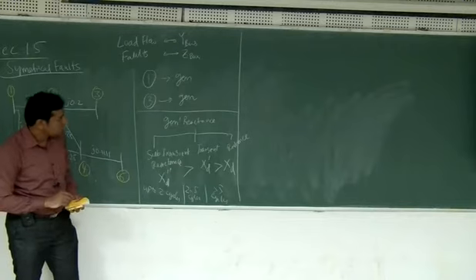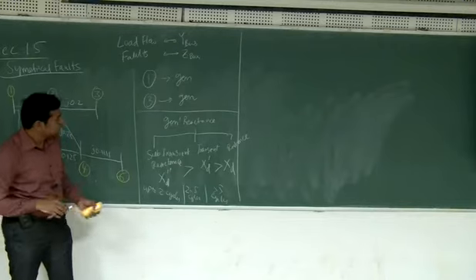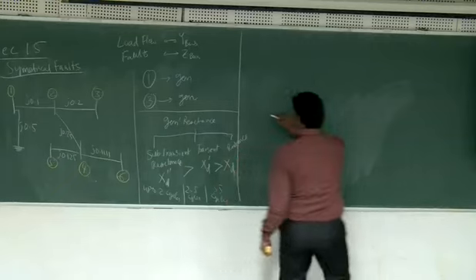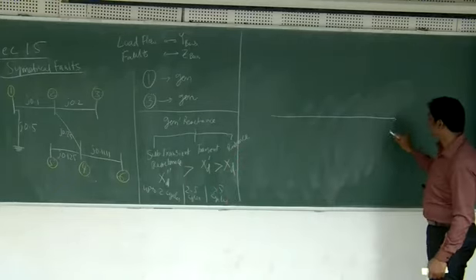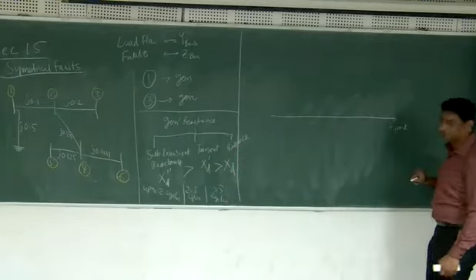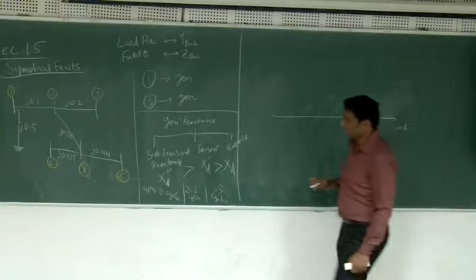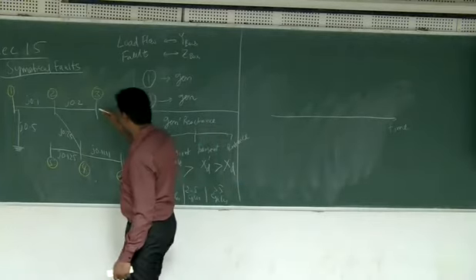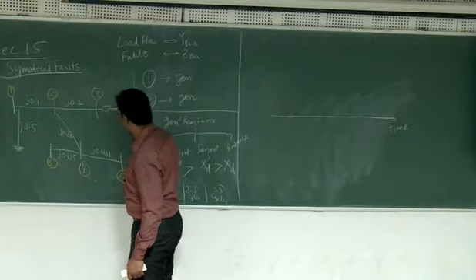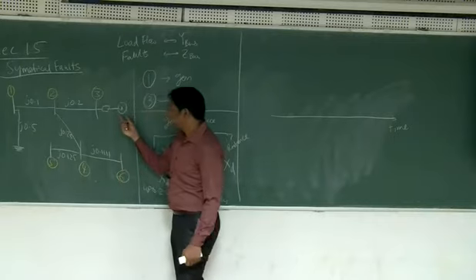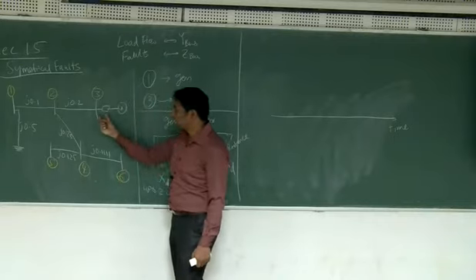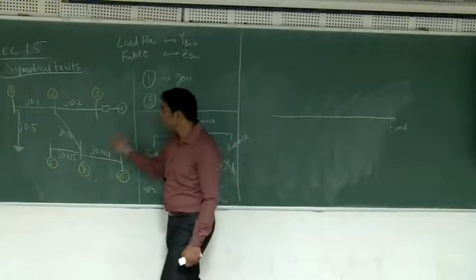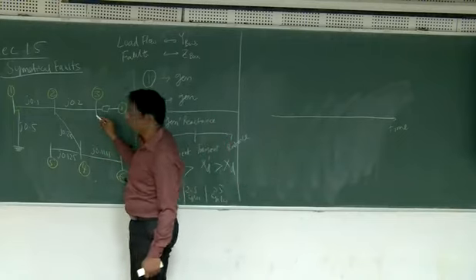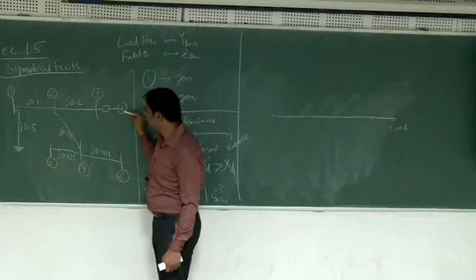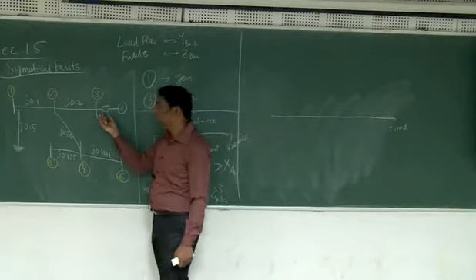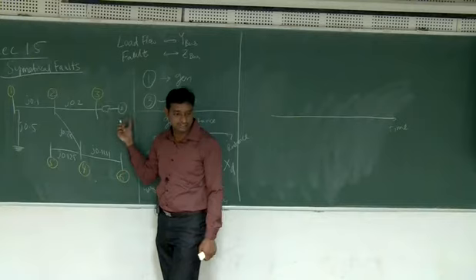Okay, I think at this time we can also discuss what actually happens. Let's say this is my time axis. Consider some part of the network. Let's say this is a network, and then there is a circuit breaker here, and then there is a generator here. This generator is generating power, and then there is a circuit breaker. So if there is a fault at 2 or a fault at 3, a large current will flow from this generator, and this circuit breaker will detect that, and then it will disconnect the generator.